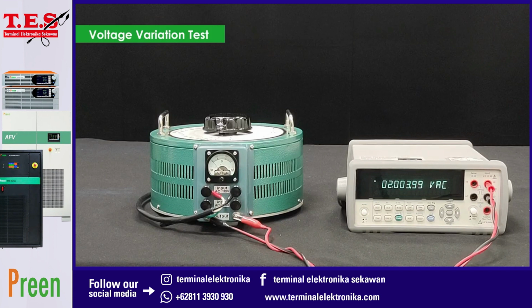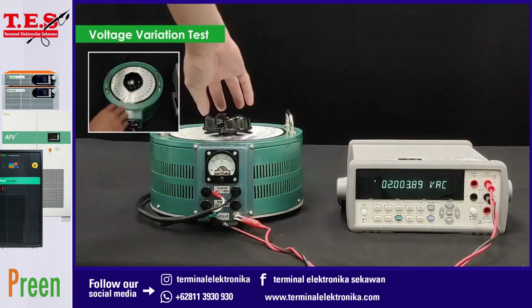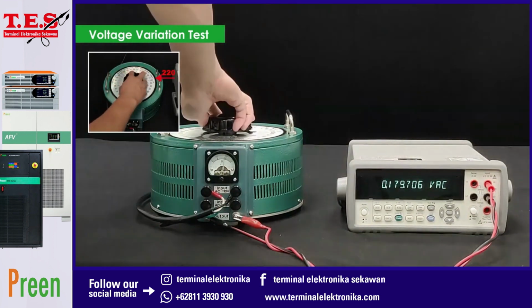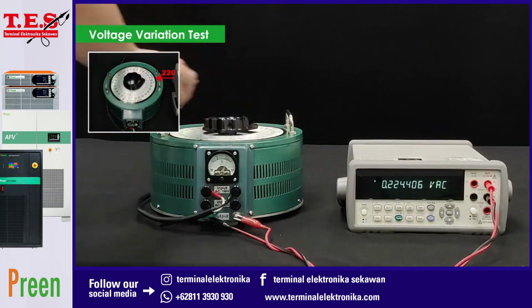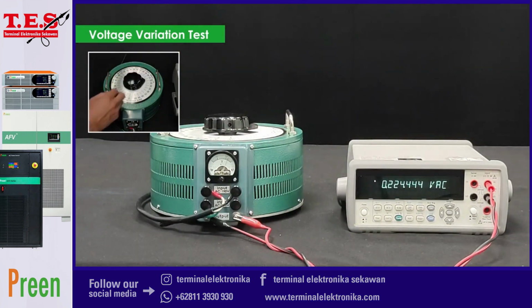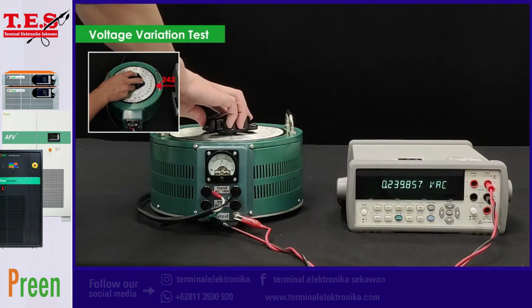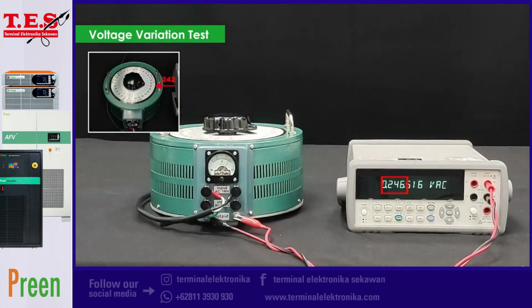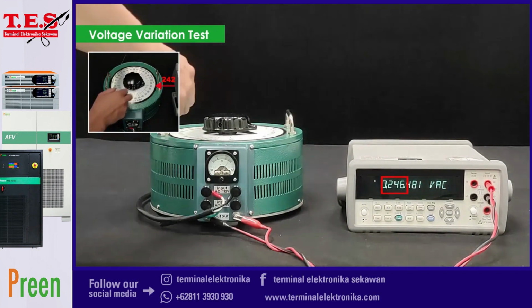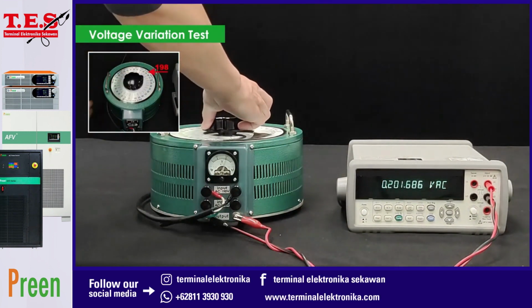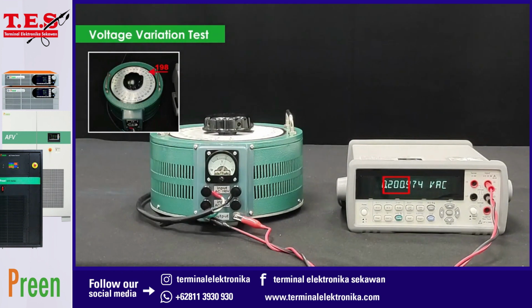Now we will conduct 3 different applications through a variable transformer and programmable AC sources. Let's start with the voltage variation test. We have set the output voltage to 220 volts and would like to have the voltage to be 10% more, which is 242 volts. Now, the meter reads 246 volts. When we switch down the voltage 10% to 198 volts, the meter shows 200 volts.